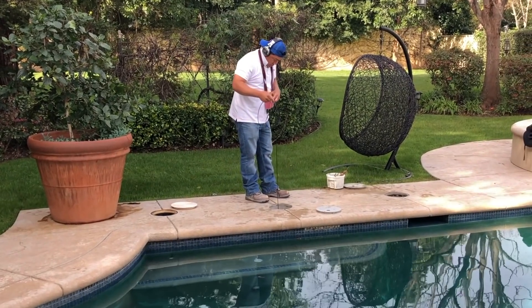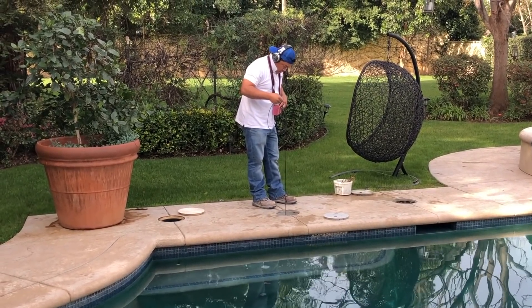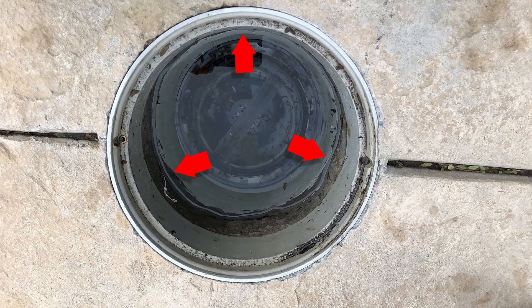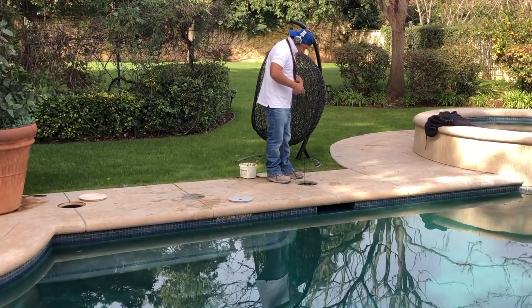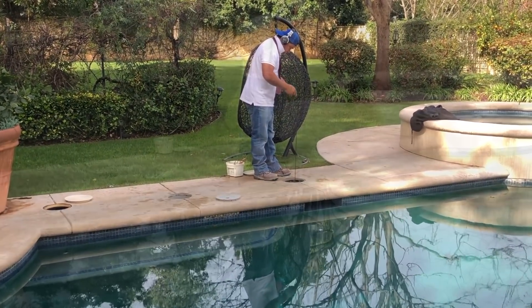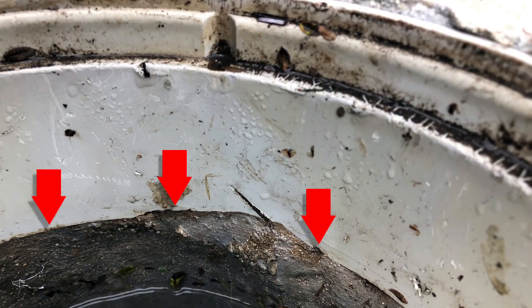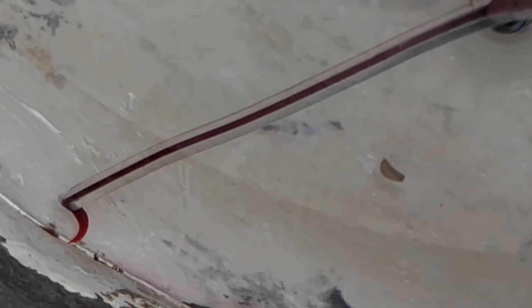Here's the self-cleaning canister — and we found ourselves a leak in the seam of the self-cleaning canister. We're going to keep checking everything to make sure nothing else is leaking before we come back and show you the actual leak. Checking the equalizer. We're pointing back out that it is the cleaning canister. We can see the crack, and you'll actually see the debris. This is where there was a crack in the actual canister — cracked in multiple areas — and here's where it's taking dye. This is exactly where we heard it. You can see how we did a quick leak detection: we heard the leak with the pool scope and backed it up with a dye injection.